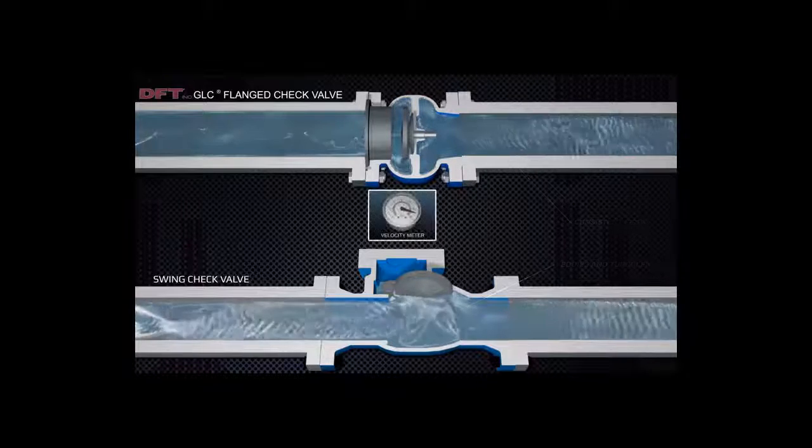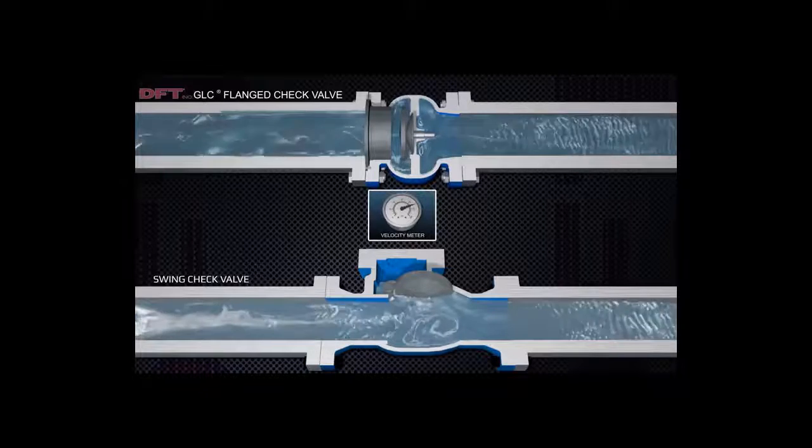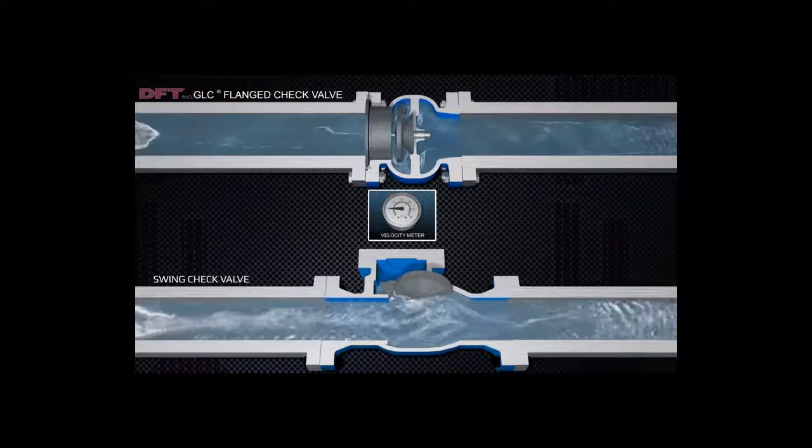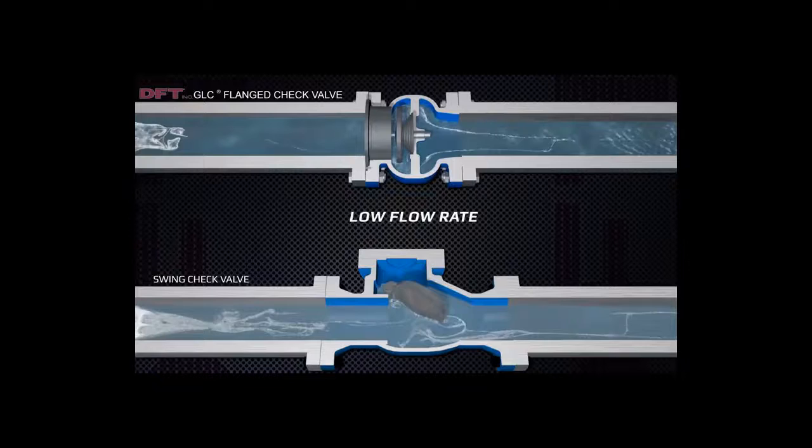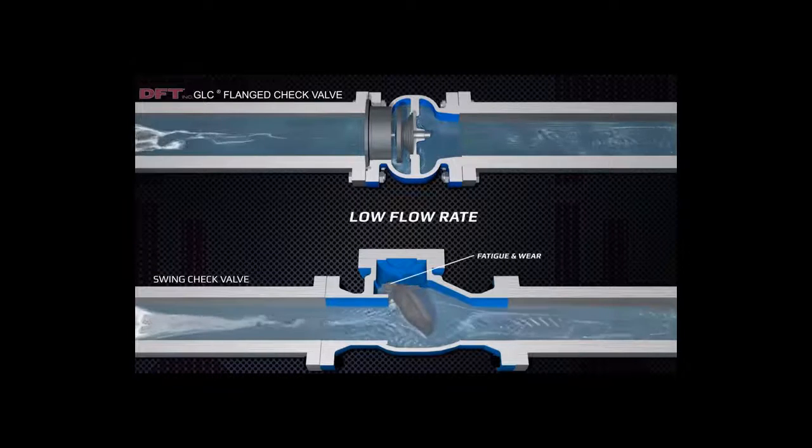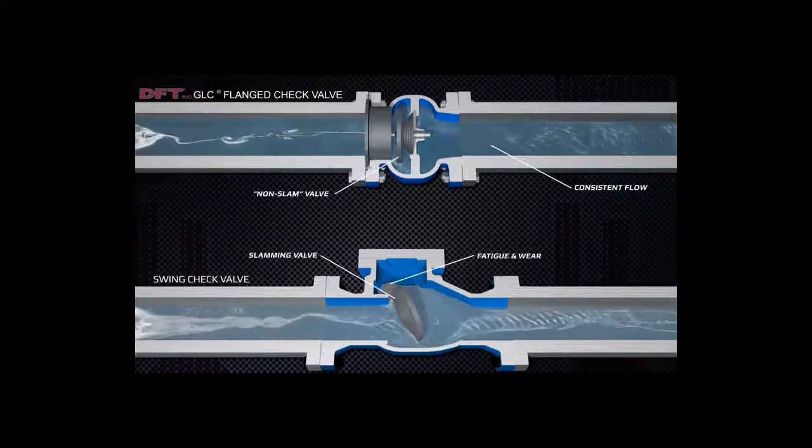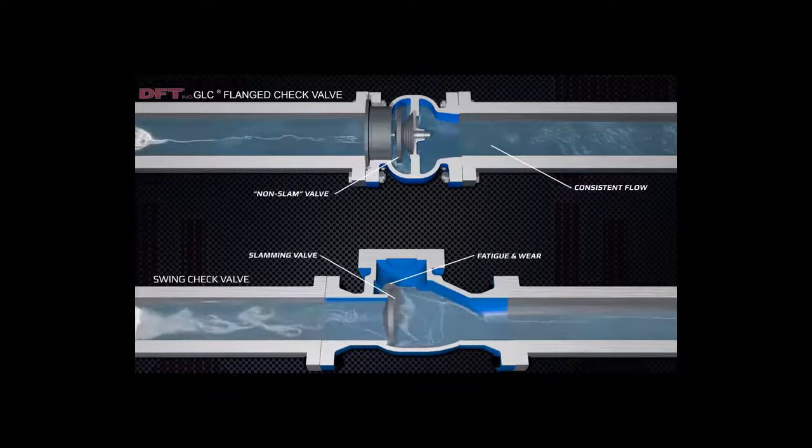During a low flow application, the GLC maintains a consistent flow, whereas the swing check is unstable and constantly in motion. The motion and slamming of the swing check valve can cause fatigue and wear on the hinge pins.